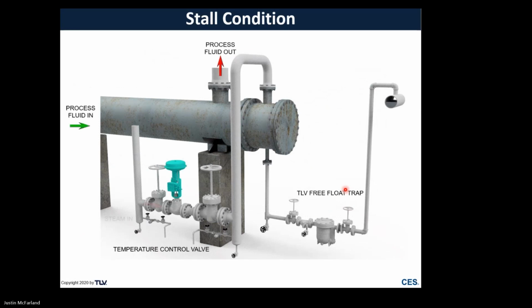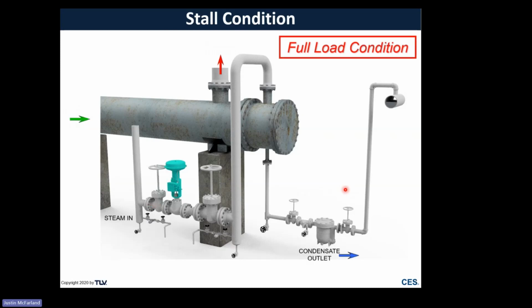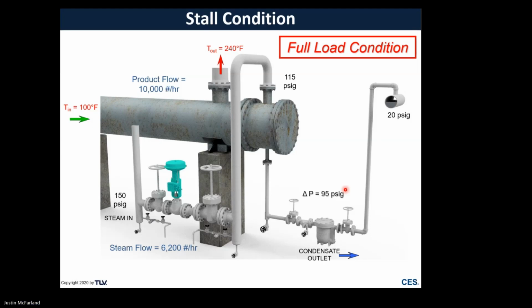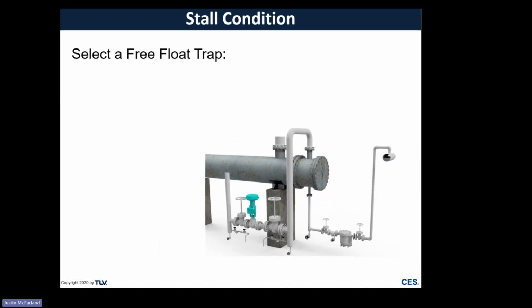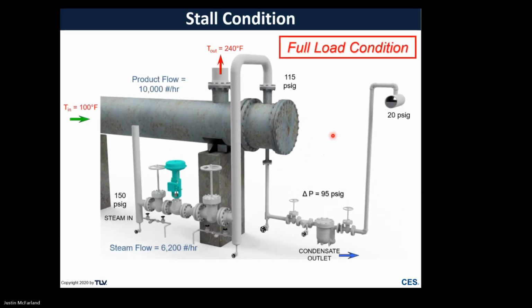So got an example here. I'm going to go through this just very, very quickly to save on some time here. So this is what I would consider a full load condition. One scenario here where we've got inlet temperature of 100. We're trying to increase temperature out to 240. We've got our steam inlet control valve, fixed outlet pressure of 20, product flow rate of 10,000 pounds an hour, steam flow of 6,200. So looking at all those, we can estimate a positive differential pressure of 95 psig.